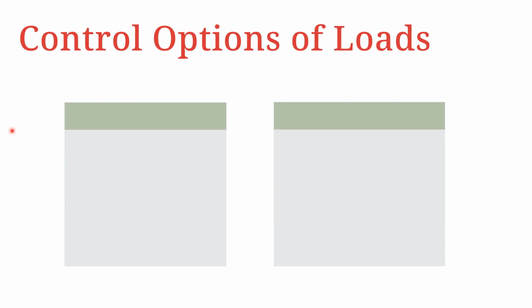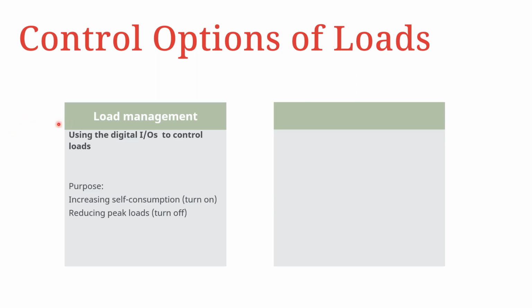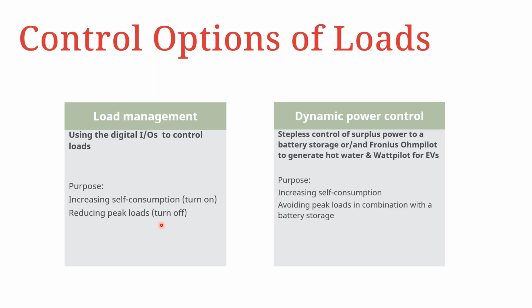So in terms of the control options, we have 2 key control options. One is what we are referring to here as load management, which can be achieved by use of the 4 digital IOs that I've just mentioned. And here the purpose would be to increase your self-consumption, which would trigger an on signal, and also reducing the peak loads, which means that you turn off something that would consume outside of your, let's say, PV generation. And then you have the possibility also as a control option for dynamic power control, which means that you are able to do stepless control of the surplus power. And this can be fed into a battery storage or used to generate hot water using the Fronius Ohmpilot. In addition to that, you can connect a Wattpilot for EV charging, and then you also have the control of surplus energy from the inverter.